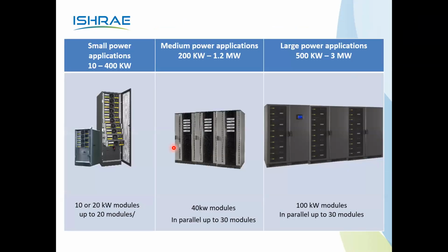Coming to the modular UPS. Here you can see there are a number of slices. Multiple modular ratings are available: small ratings, say 10 kilowatt, 20 kilowatt and 40 kilowatt modules, as well as 100 kilowatt modules. Once again, I would like to highlight that the modular UPS is meant for scalability. As and when required, you can increase the UPS capacity. No need to go for a higher capacity from day one.